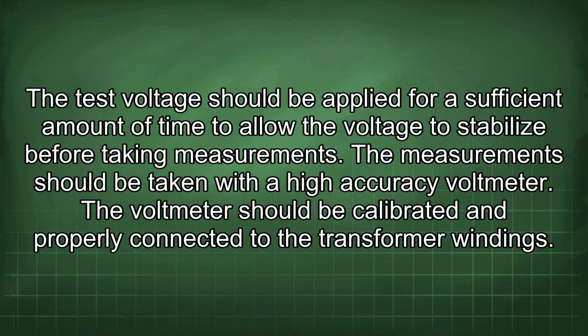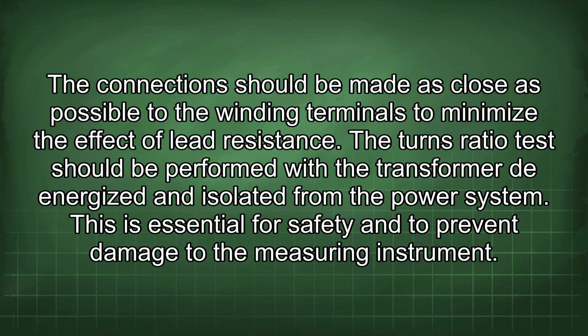The measurement should be taken with a high accuracy voltmeter. The voltmeter should be calibrated and properly connected to the transformer windings. The connection should be made as close as possible to the winding terminals to minimize the effect of lead resistance.